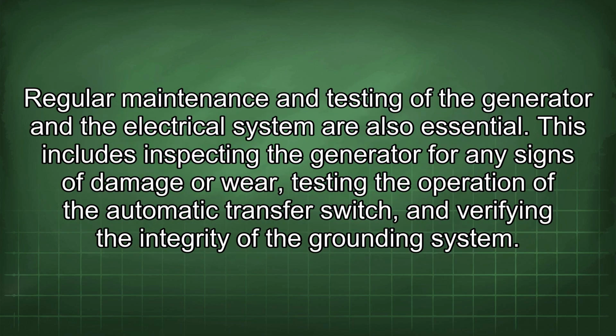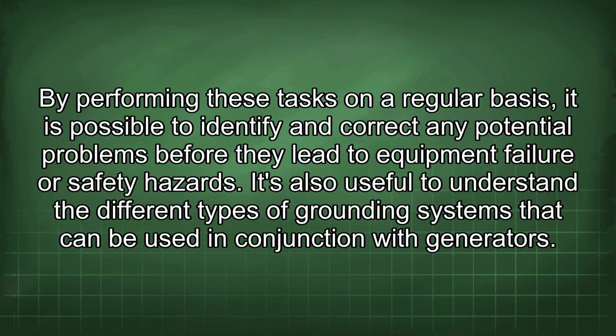Regular maintenance and testing of the generator and the electrical system are also essential. This includes inspecting the generator for any signs of damage or wear, testing the operation of the automatic transfer switch, and verifying the integrity of the grounding system. By performing these tasks on a regular basis, it is possible to identify and correct any potential problems before they lead to equipment failure or safety hazards.